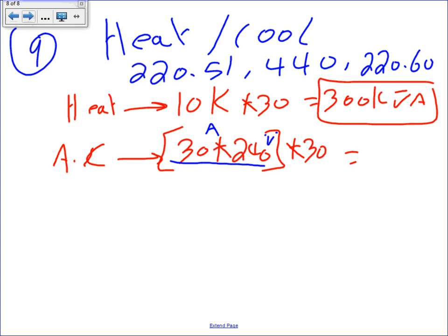This is amps, this is voltage. So how do you convert amps and voltage into volt-amps? Multiply them by each other, the power law. So I took the volt-amps of each air conditioner. They're not giving it to me. I have to calculate it based on the amps multiplied by the voltage, multiplied by how many units. The second 30 is the number of units. I should have picked a different number. Everybody knows the difference between the first 30 and the second 30. Okay, what's the answer? 216,000. The answer is 216 kVA.